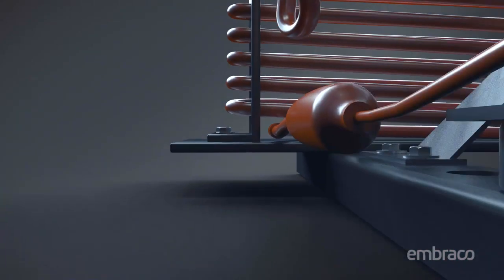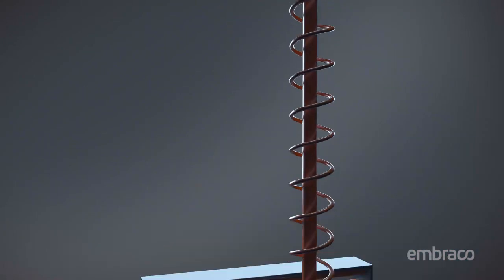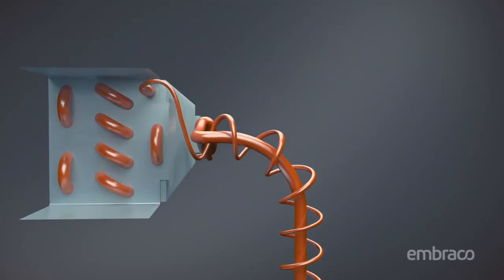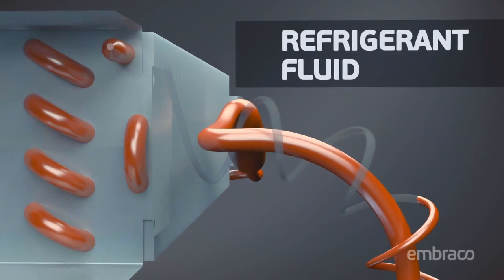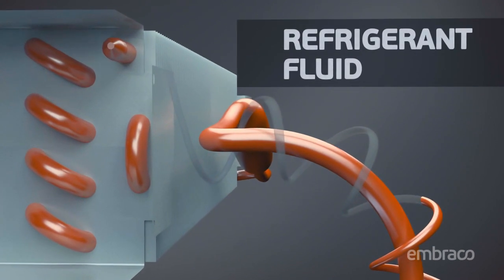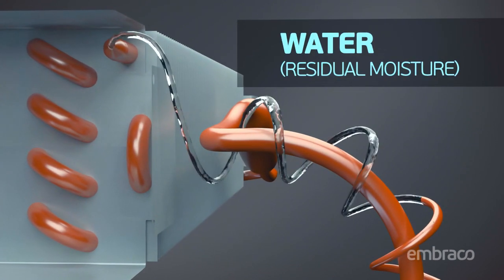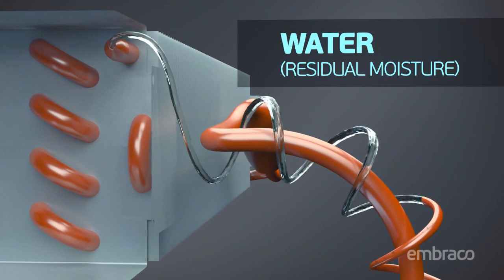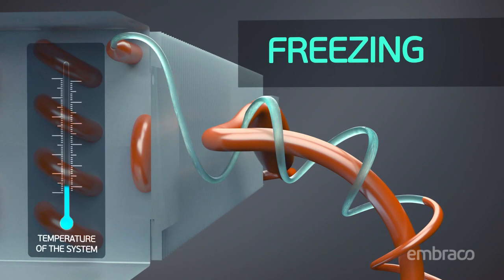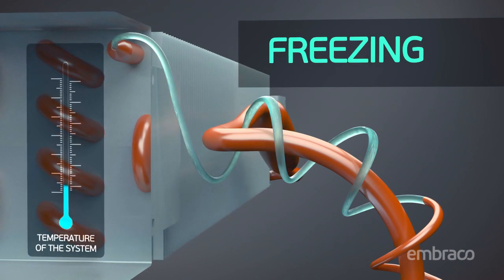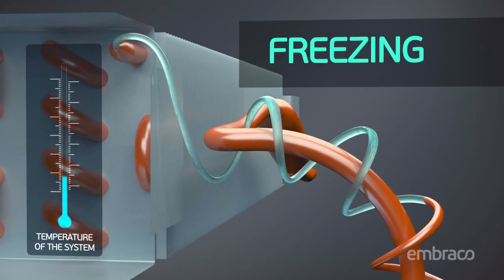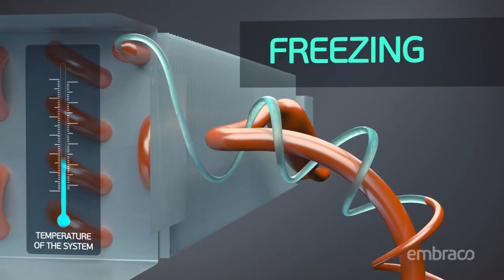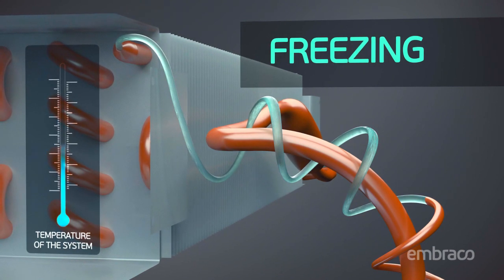See below what can happen. In the refrigeration system capillary tube, clogging will occur due to residual moisture freezing in the small passage. The capillary will be blocked and the refrigerator will stop operating properly and heat up.